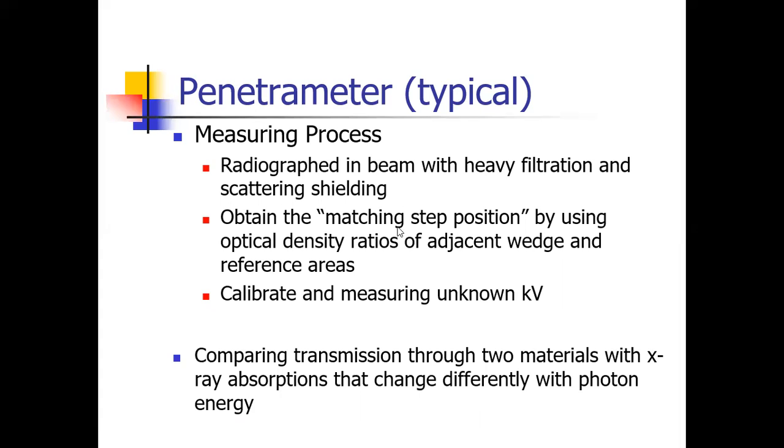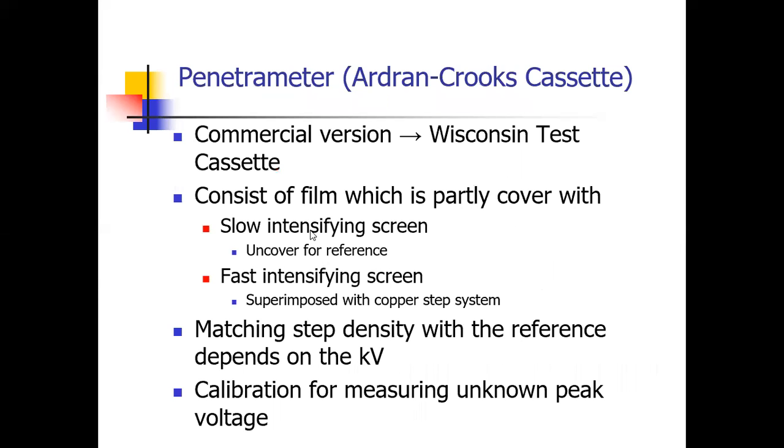You'll obtain the matching step position by using optical density ratios of adjacent wedge and reference areas, and calibrate and measure the unknown kV. So again, you're comparing transmission through two materials with X-ray absorptions that change differently with photon energy.